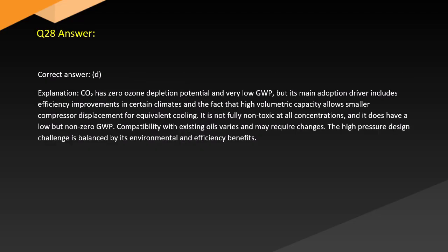Answer. Correct answer. D. Explanation. CO2 has zero ozone depletion potential, but its main adoption driver includes efficiency improvements in certain climates and the fact that high volumetric capacity allows smaller compressor displacement for equivalent cooling. It is not fully non-toxic at all concentrations, and it does have low but non-zero GWP; compatibility with existing oils varies and may require changes. The high pressure challenge is balanced by its environmental and efficiency benefits.